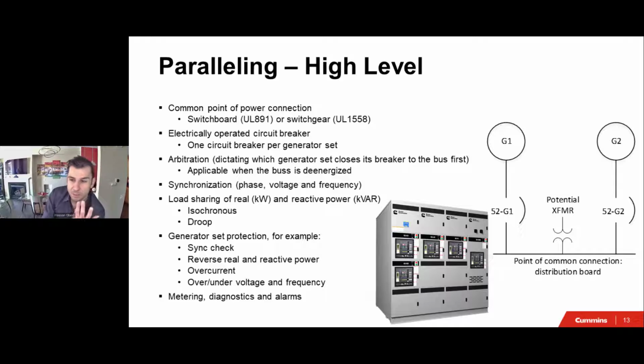If one of them closes to the bus first, because the bus in this case is de-energized, let's say it's a black start, this is why we need the arbitration. And once one closes to the bus, the next thing we need to do is synchronize. So we need to synchronize the phase, voltage, and frequency.